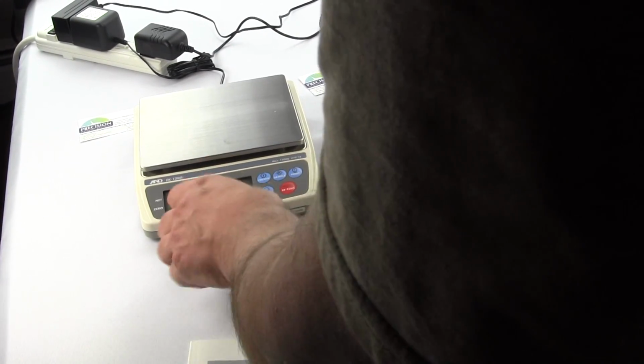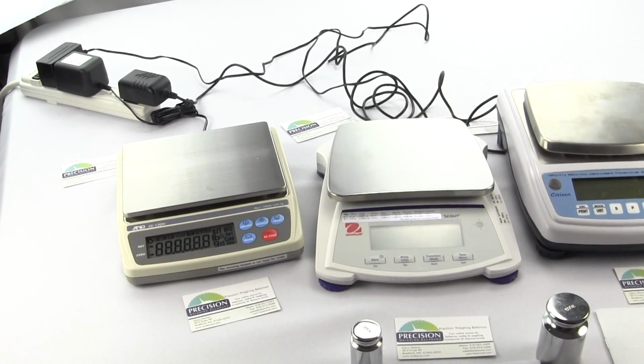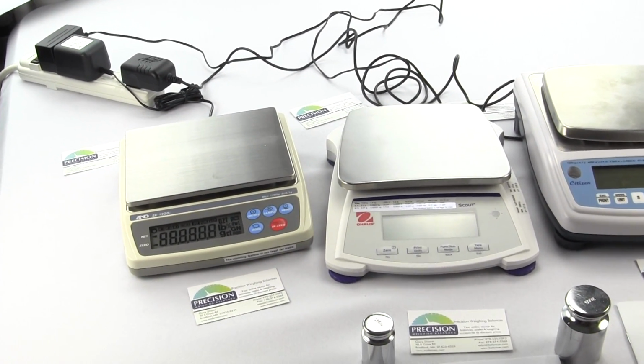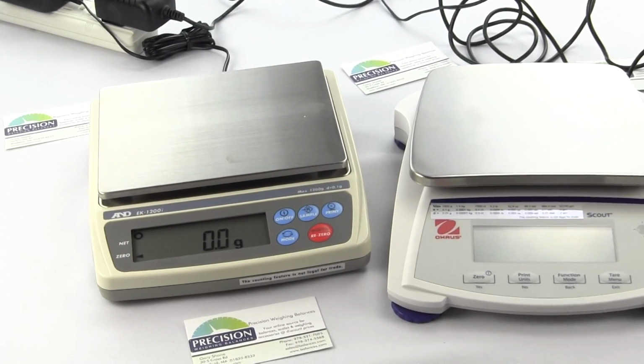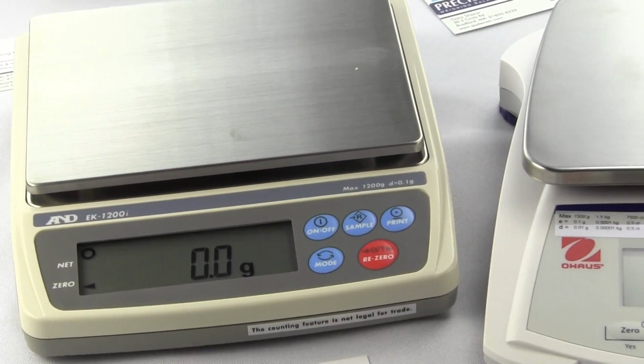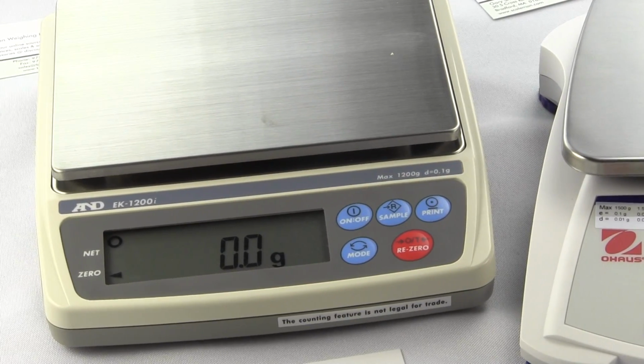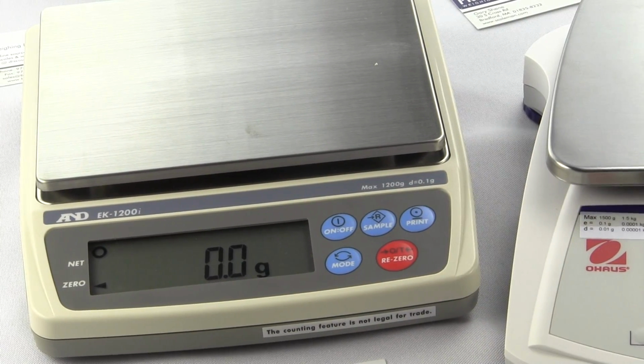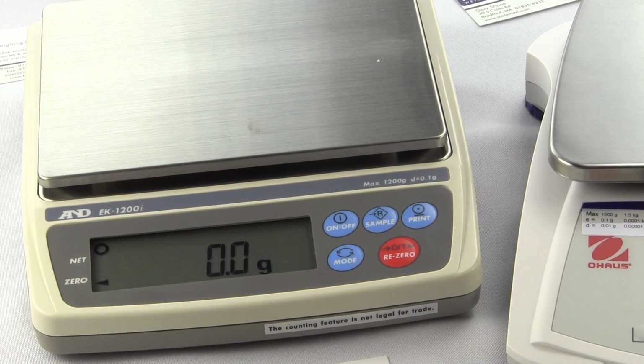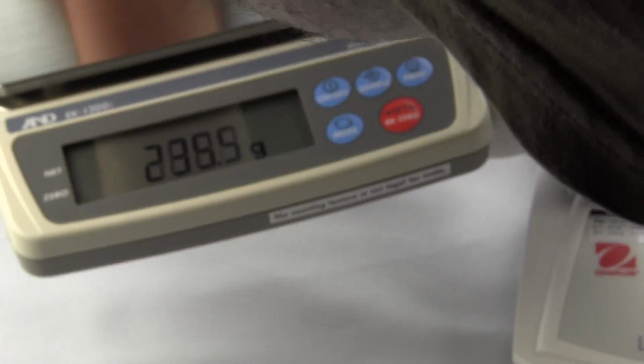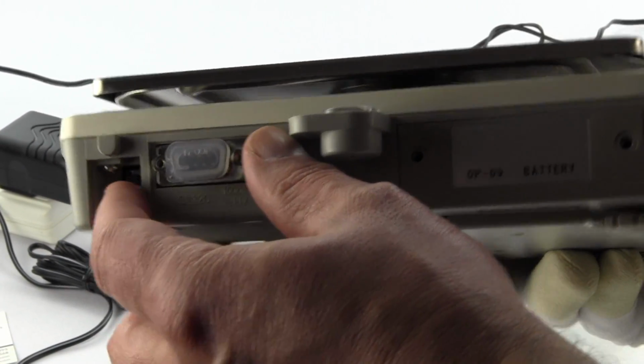So I have my 3 scales. Let's do calibration. Okay, on the A&D EK-1200i, it's user selectable, and the default is 1200 grams, but I set it up for 1000 grams just because I wanted to calibrate all 3 of these scales with the same weight. So since it's legal for trade, on the back of the scale, we have to open up the calibration cover, and there's a little button here that has to be pressed. So it's legal for trade, and weights and measures typically would put a wire through that.